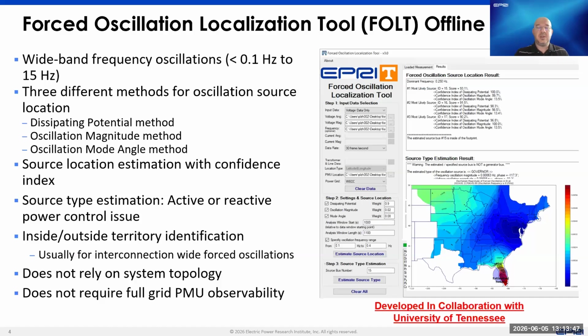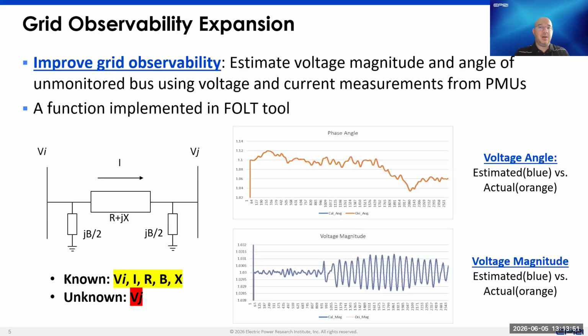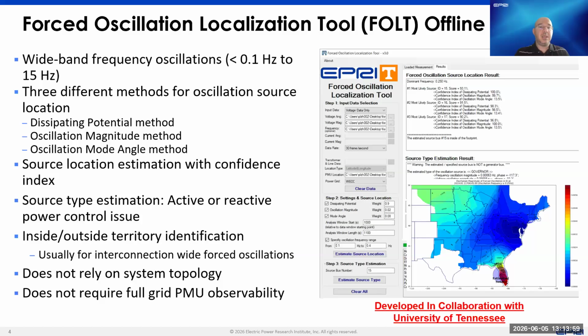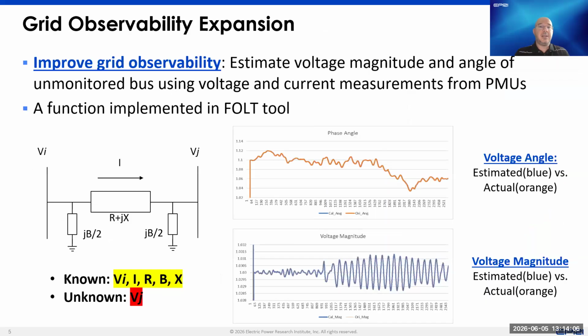That's one of the EPRI tools that we use for this study. So the tool is basically using voltage. We can use different types of data: voltage, frequency, and currents. The currents, which we used in this case, help increase the observability of the grid. So, for example, if there is a bus unobservable, let's say on the left-hand side, and we have a PMU here with the voltage and the current flowing through that line, then we can estimate the voltage here. That's a function implemented in the tool that increases the observability, and that was helpful also in this study, as I will show in the slides later.